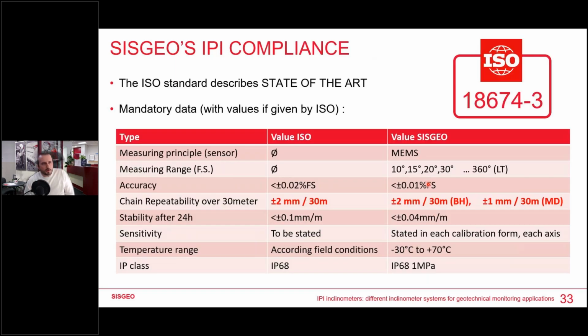So we are proud, and for us it's very important to show you that our systems are compliant with the ISO norm. This ISO describes the state of the art for all borehole inclinometers. That means the norm doesn't make a difference between manual system and automatic system. The parameters that are mandatory from the ISO norm are exactly the same from the manual to the automatic. So we are proud to provide systems that are completely compliant in automatic or manual mode.